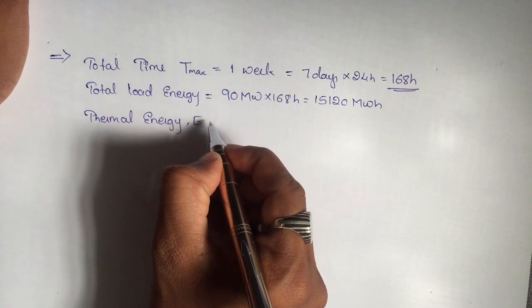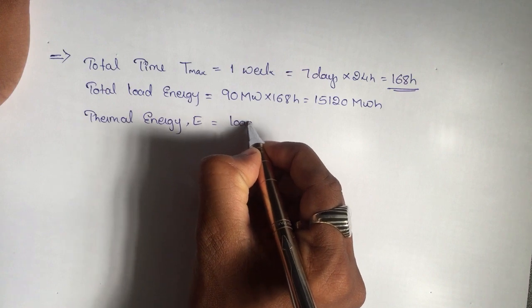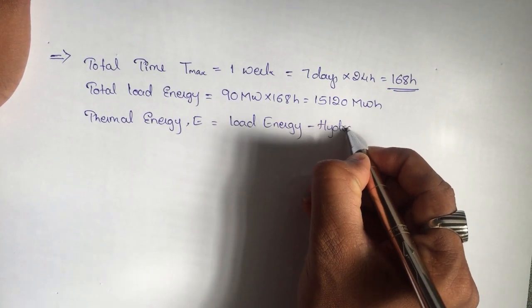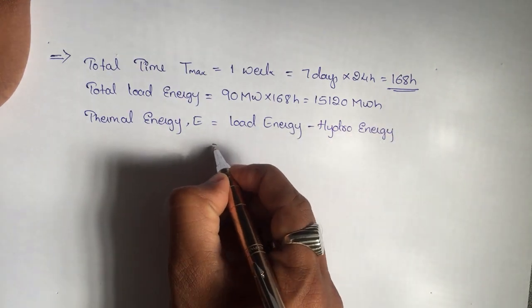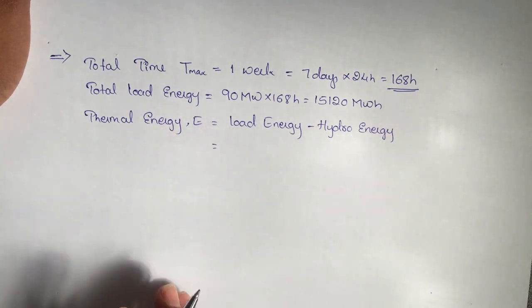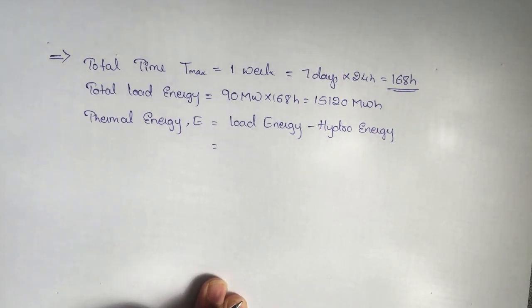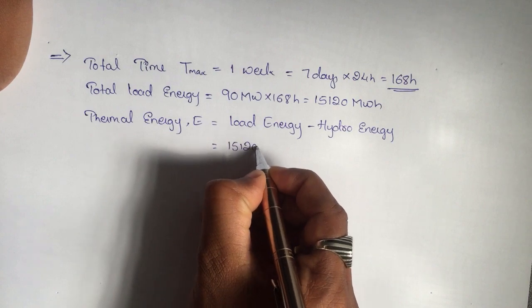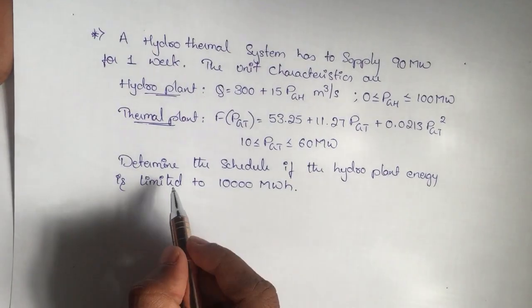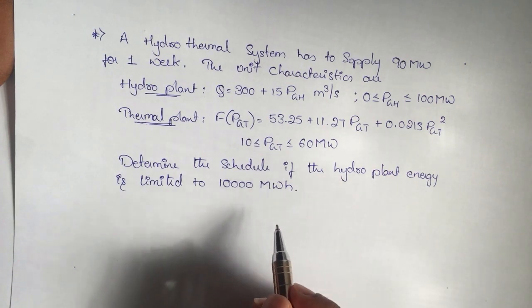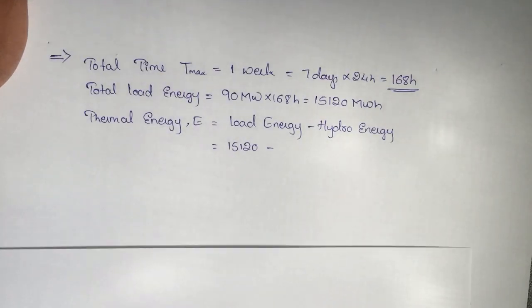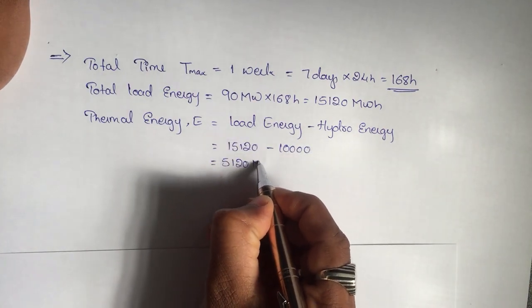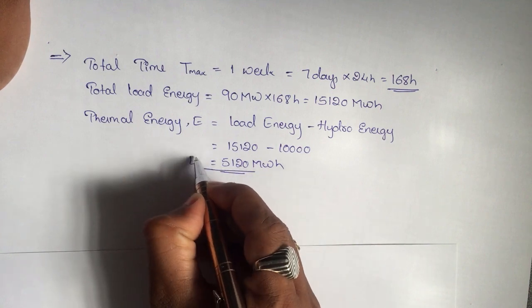The thermal energy E is equal to load energy minus hydro energy. The total thermal energy we need to generate equals the total load energy minus the hydro energy. Load energy is 15,120 megawatt hour minus hydro energy of 10,000 megawatt hour, giving E = 5,120 megawatt hour.